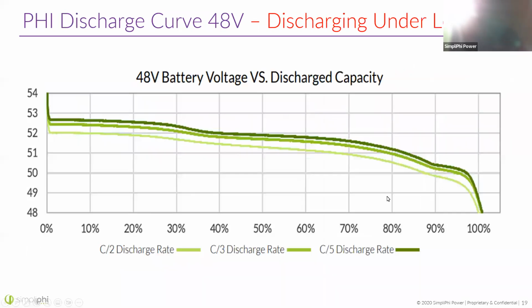So that's what I'm going to show you here. This is a battery in different states of load. A C/2 discharge rate is the max continuous rating for these batteries. When I discharge at C/2, I'm discharging fast enough to fully deplete it in 2 hours. At C/3, I'd start with a 100% state of charge battery and fully deplete it in 3 hours, so it's a little less current.